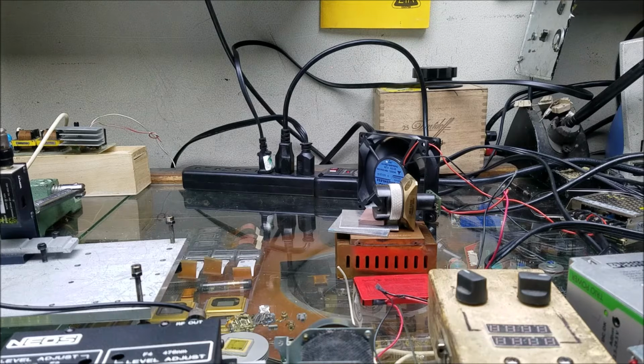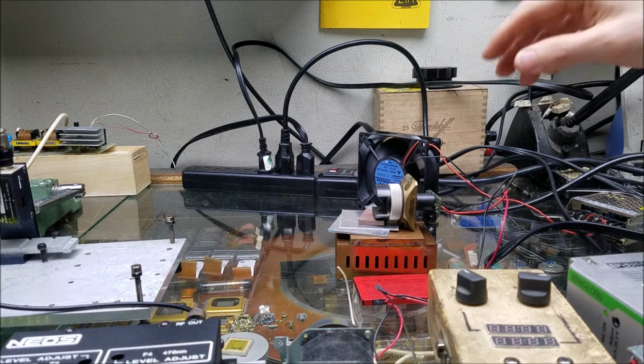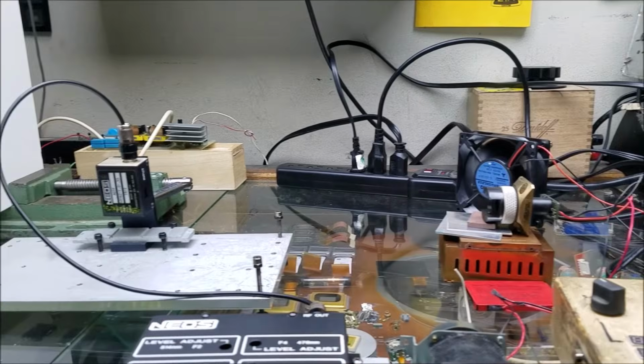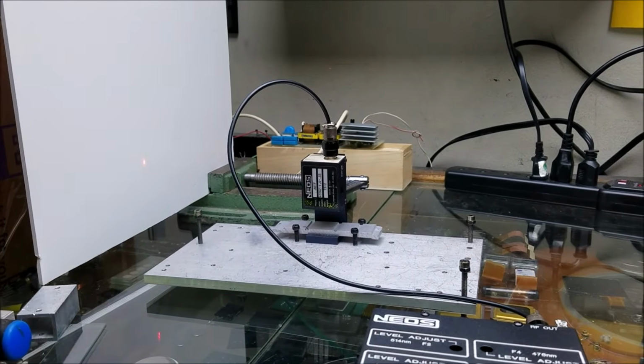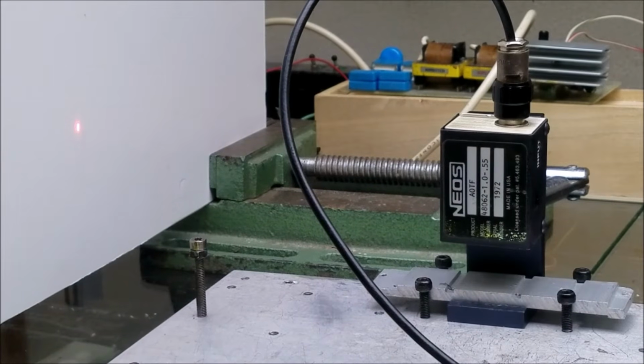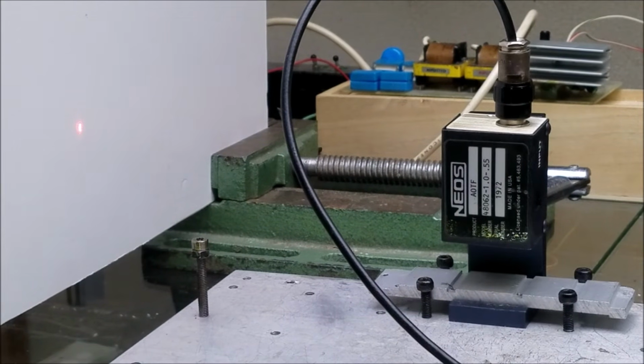At this point, I have the Acousto-Optic Modulator set to the 647 nanometer setting for the red. And the first laser diode that I want to test out is this one right here. Not exactly sure what the frequency is, but I'm pretty sure it's 650 nanometers just by looking at it. It's a pretty mid-range red. To test that out, I have it going through the Acousto-Optic Modulator, and I have my output right there. And I have the modulation voltage going into the controller set at 8 volts. So I have a linearly polarized laser light source, and we should get above 50% as far as the efficiency.